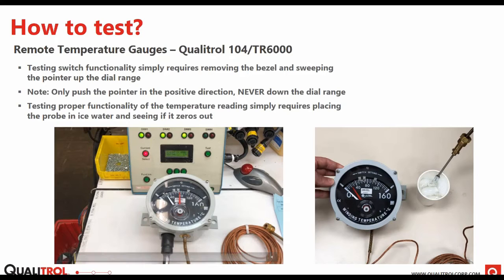So we can move on to our remote temperature gauges. This first test here on the left only applies to remote temperature gauges that we offer. Our smaller direct mount, you cannot do the same type of test. I just want to make that clear up front. It could cause some damage on direct mount, but with remote mount, this test is fine.